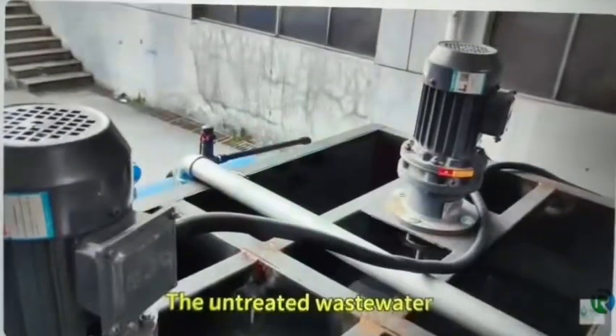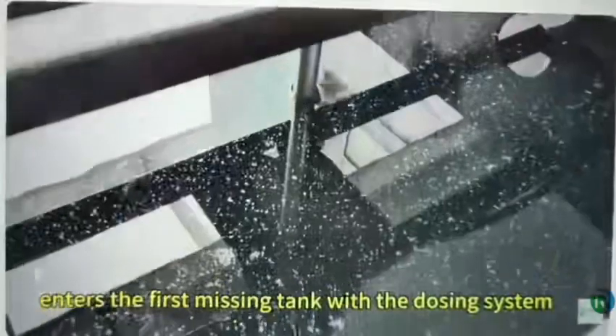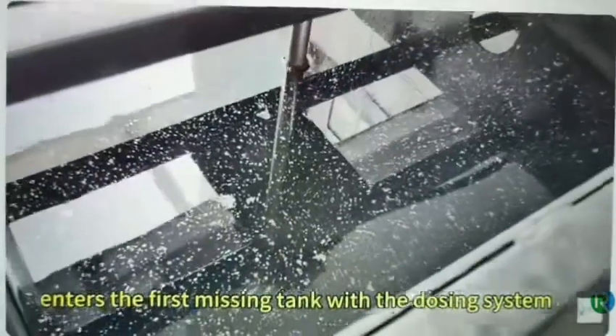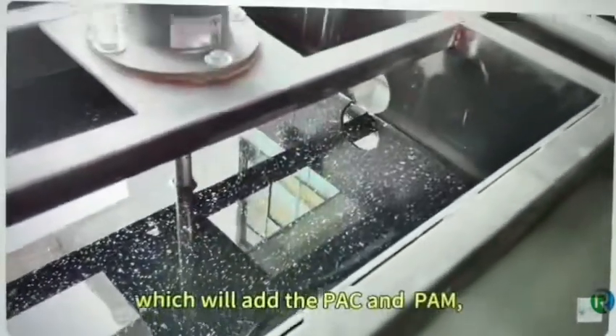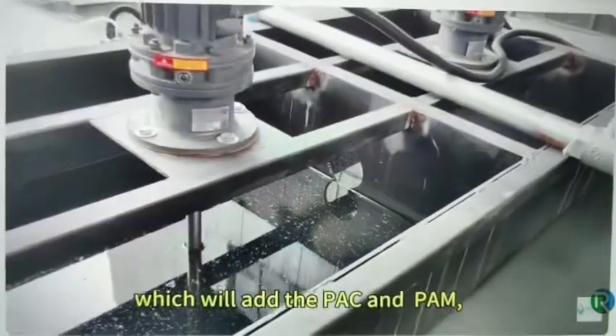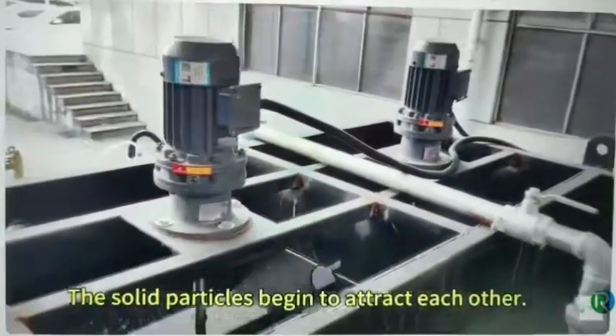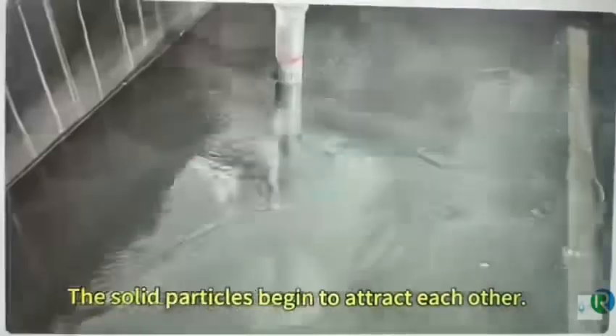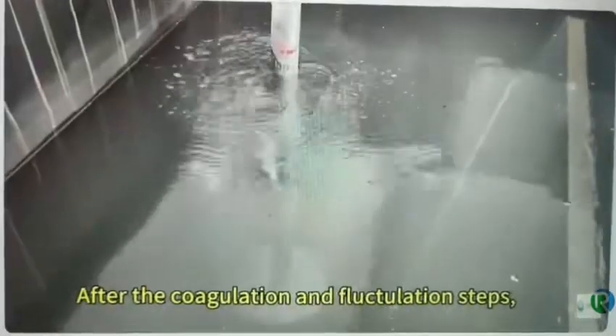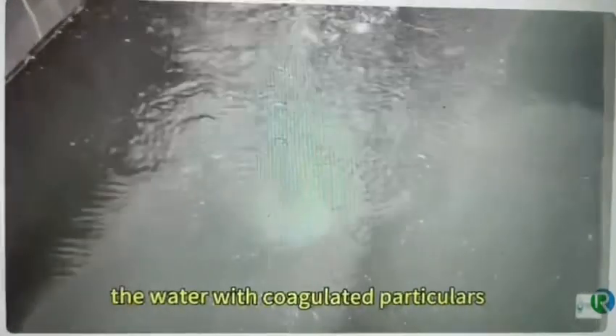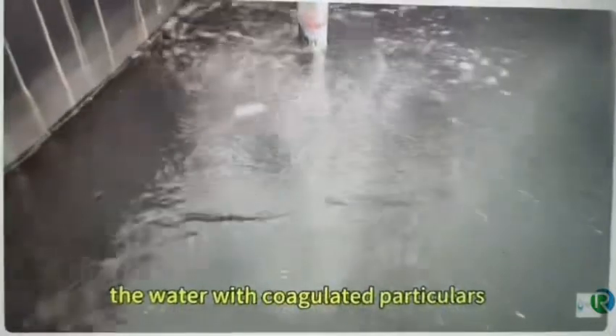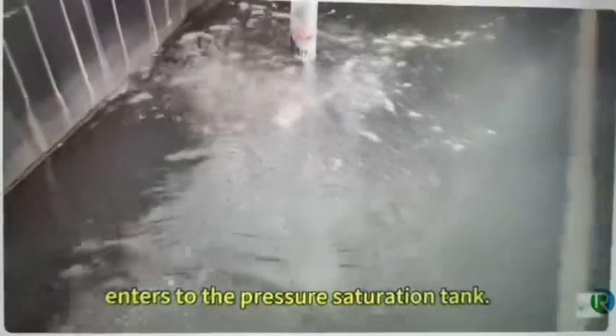The untreated wastewater enters the first mixing tank with the dosing system, which will add the PAC and the PAM. The solid particles begin to attract each other. After the coagulation and the flocculation steps, the water with coagulated particles enters the pressure saturation tank.